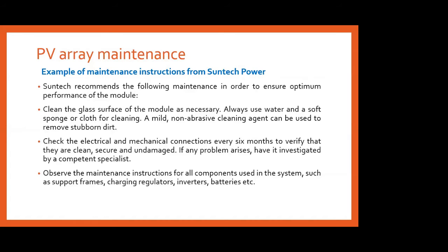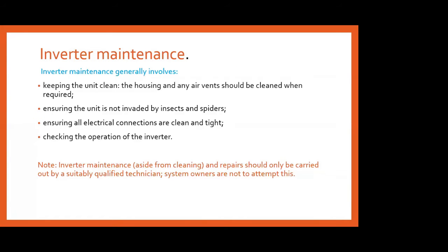Okay, and then check the electrical and mechanical connections every 6 months, to see that they are clean, secure and undamaged, and if any problem arises, have it investigated by a specialist. Also observe the maintenance instructions for all the components used in the system, such as the support frames, charging regulators, inverters, batteries, etc. Okay, this is one example, and it depends upon the geographical area, the structure and the place where people are using it. Other instructions may also be added or removed.